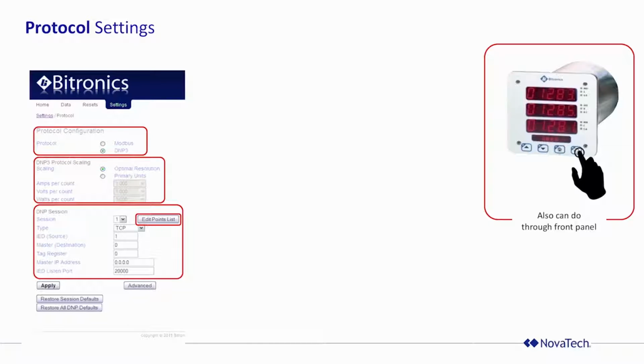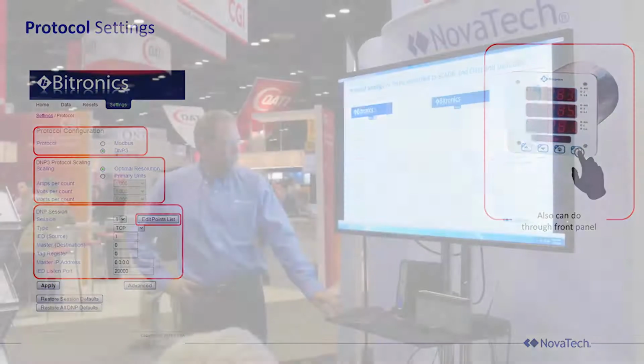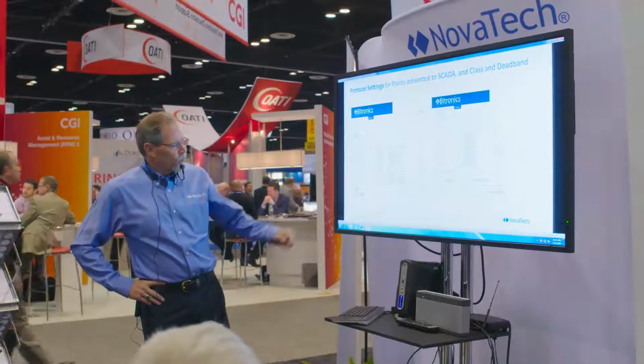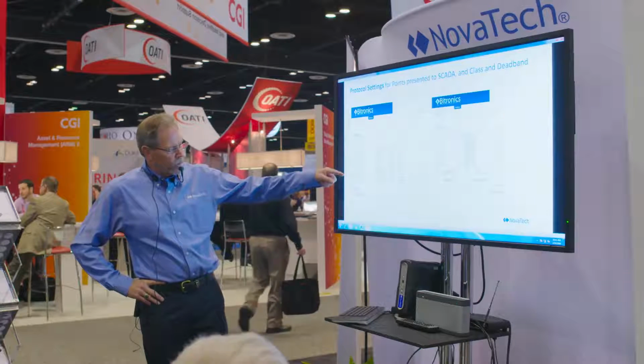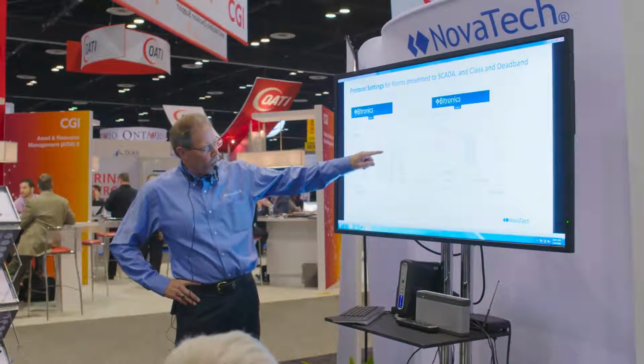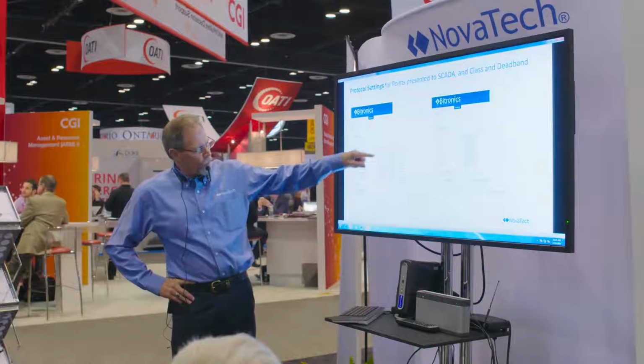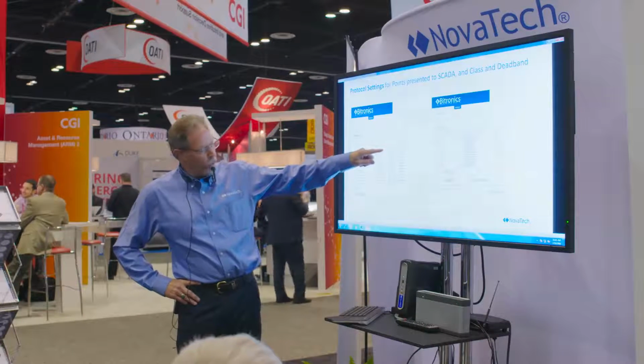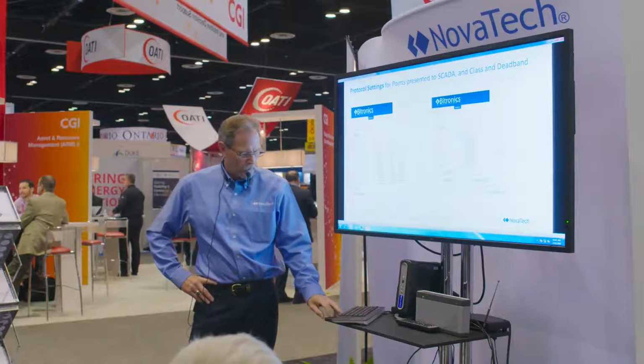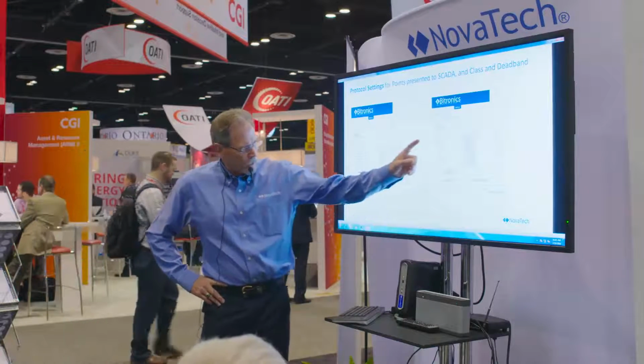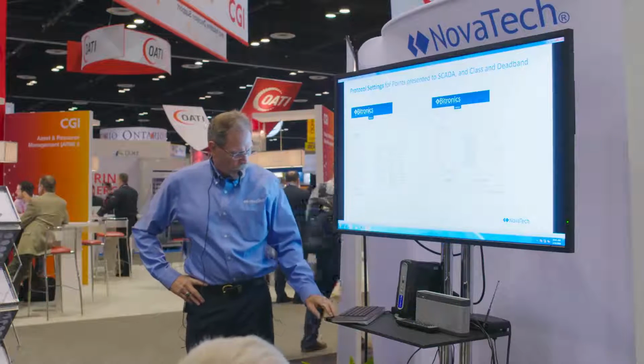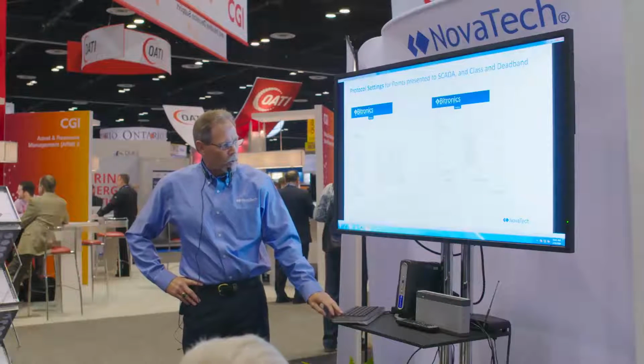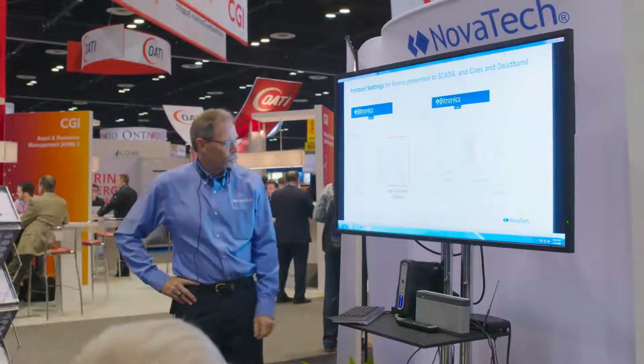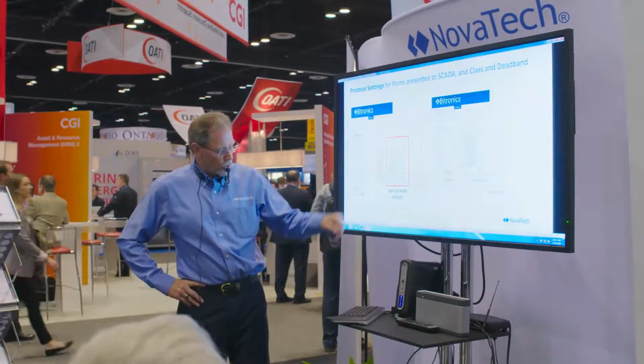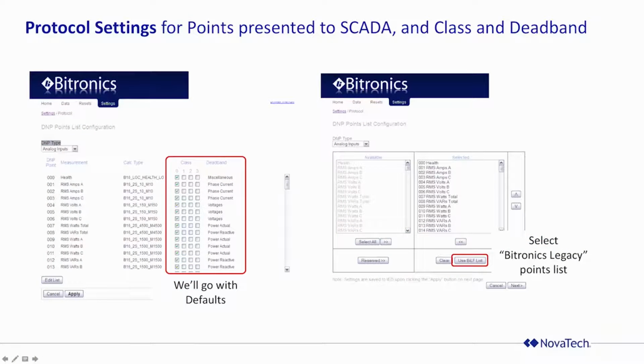The next thing I have to do is select the points list that I want to use in the meter to make available to SCADA. In this particular case, you'll see I've got a whole host of different quantities available, and all I'm going to do is go down the checklist and decide which points I want to respond to a Class 0 request, Class 1, Class 2, Class 3 request. Once I've done that, I'm going to select those values, map them over, and these are the quantities that I'll have available to the Orion or to a SCADA or an RTU. In this particular case, we'll just select all of them, which is the factory defaults.